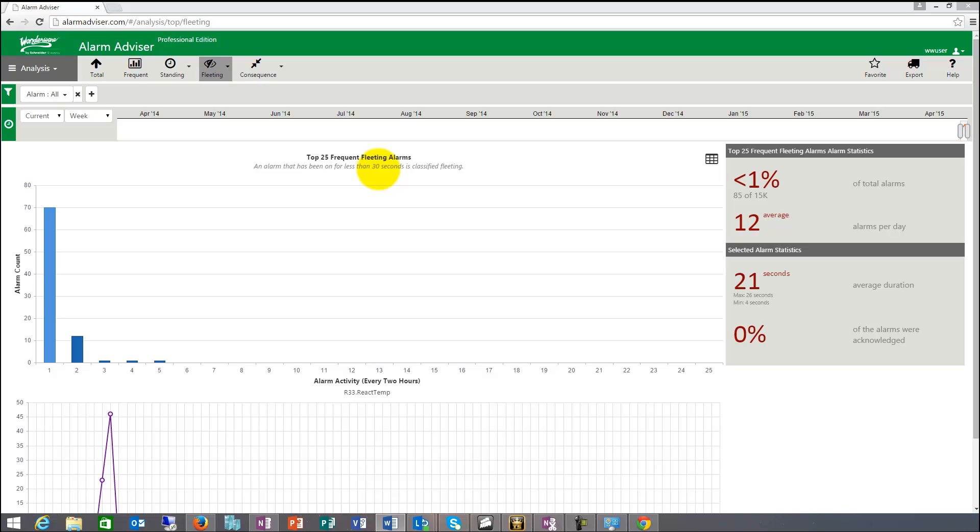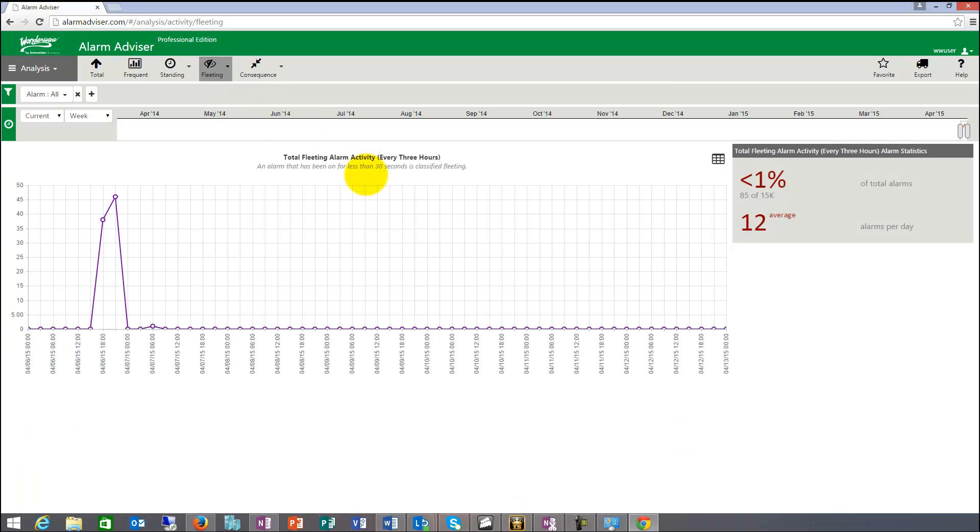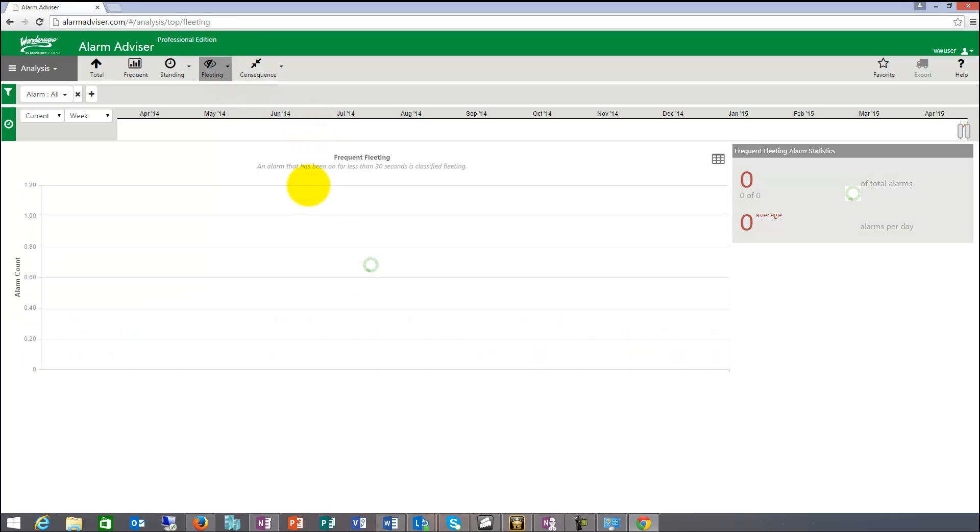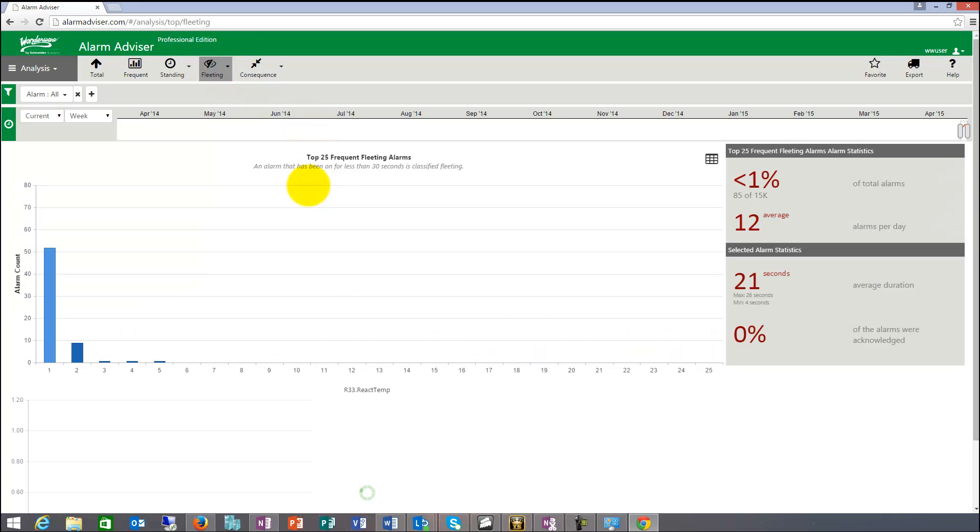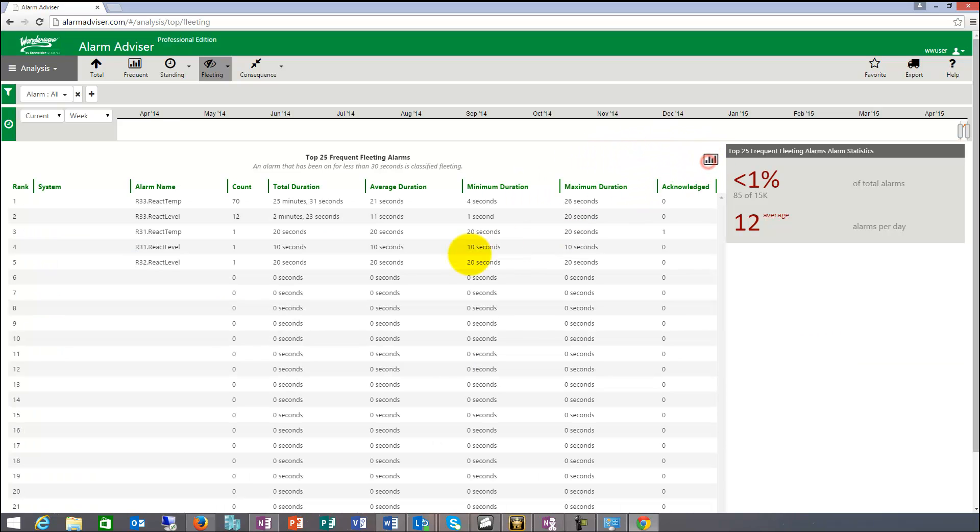So these reports you can use to put those bounce and debounce timers in and basically get them eliminated that way. So there's a total one again and then the most frequent alarms, which in this case is reactor temp. I can switch to list view again and that one has a count of 70. Total duration was 25 minutes. Average duration was 21 seconds. Minimum four, maximum 26.